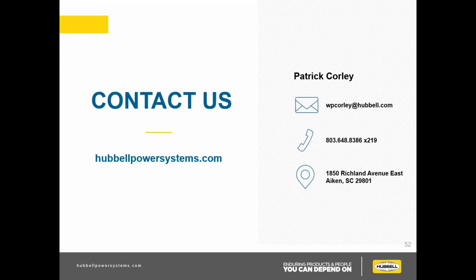All right, the next question that we have is why is the system grounding type important to consider when selecting the MCOV rating? Okay, well, the type of grounding essentially just determines the amount of neutral shift during a fault on a system. So the resulting TOV on the arrestor could cause damage unless it's sized for that TOV. This is something that we can definitely run through and help you select a proper size with your system information.